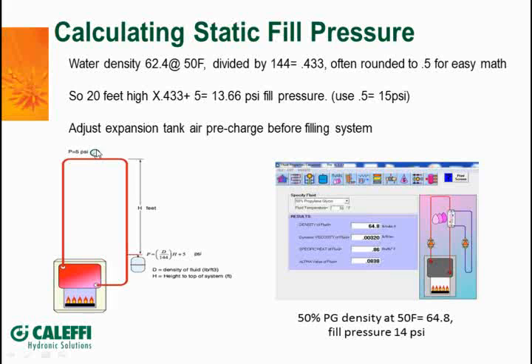A couple reasons for that is, let's say we've got a system where we've got an air vent up here. Maybe we've got a float type of air vent or even one of those little hygroscopic vents like Caleffi makes. We want to have pressure on that so we make sure that when that float floats up, there's enough pressure to seat off so we don't have any leak or any drip out of it. So we're going to use the 5 pounds at the highest point in our system as our number here as we work through this formula.